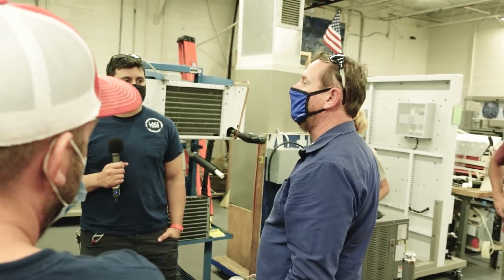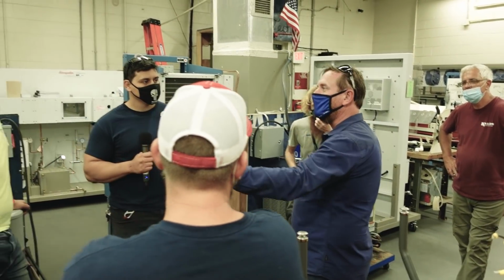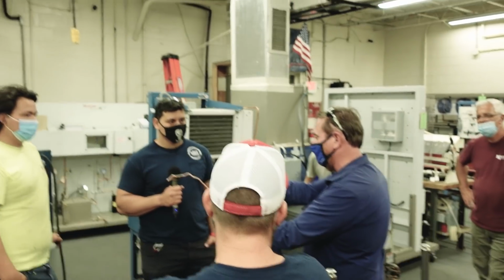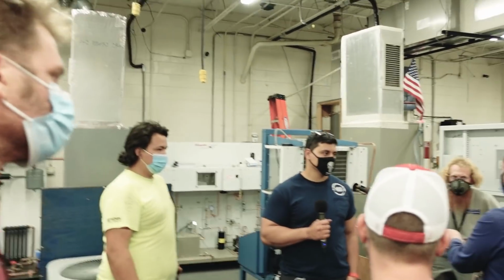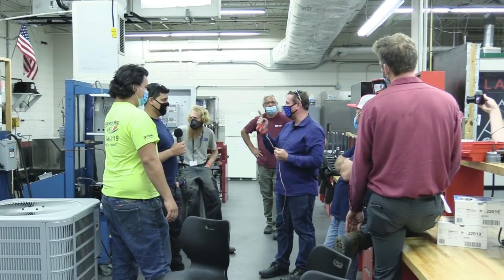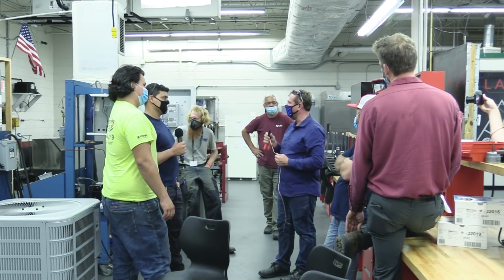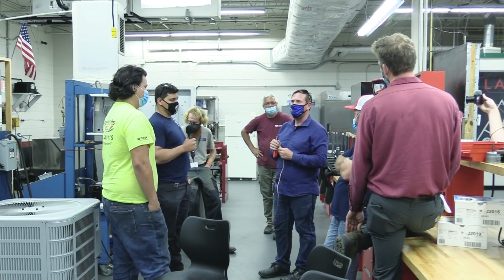Let's say you don't know what your contactor should be. Go to the truck, grab a new one. Let me check it. Oh, well, look, I'm getting 10 ohms there. I'm getting only 3 here. Those contactors are pulled in. There's a lot of heat right there. It's a very thin wire. You lose the insulation on it pretty rapidly.